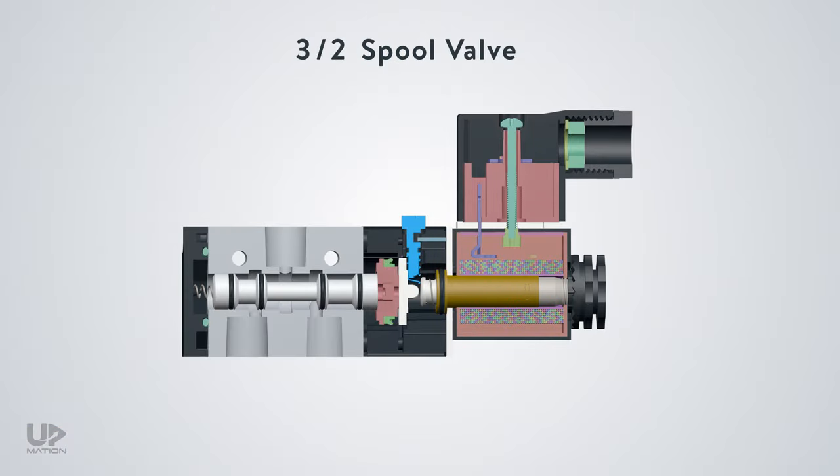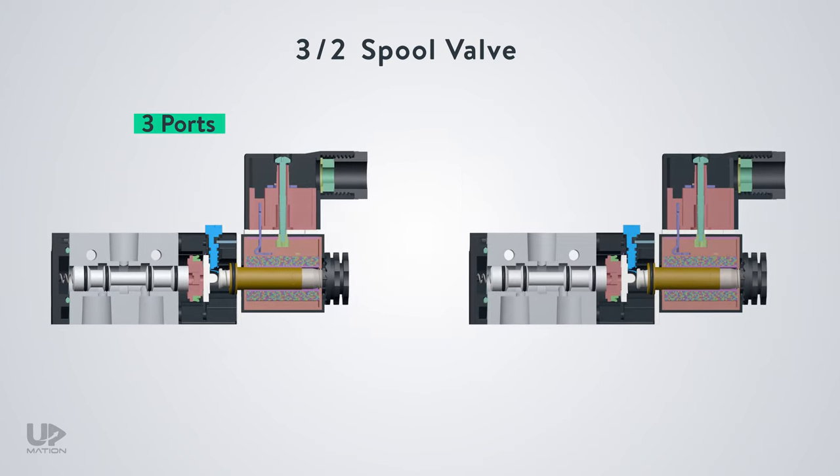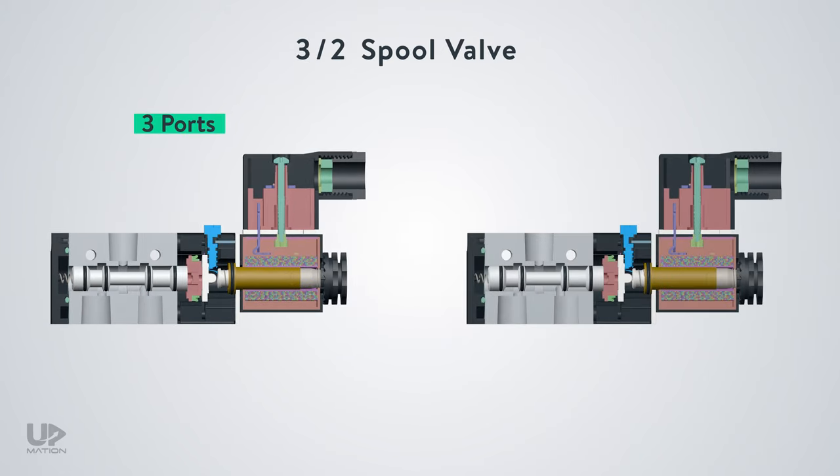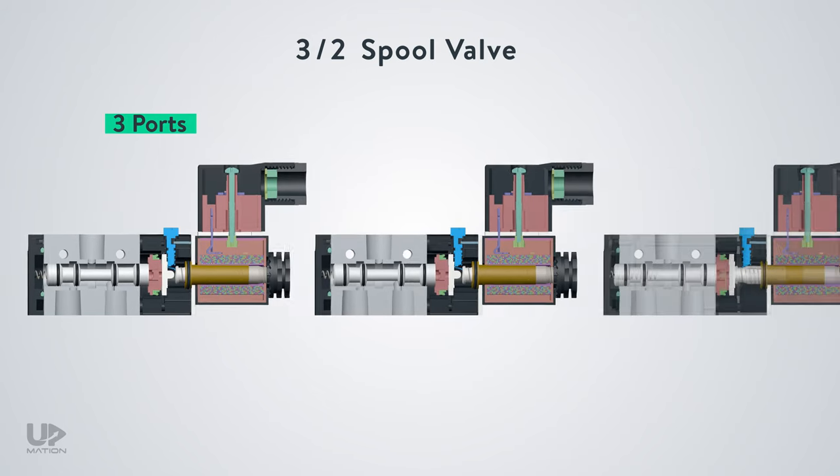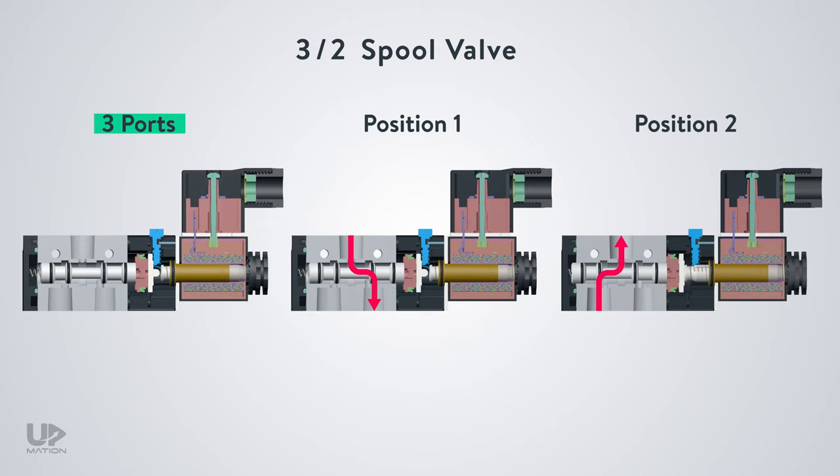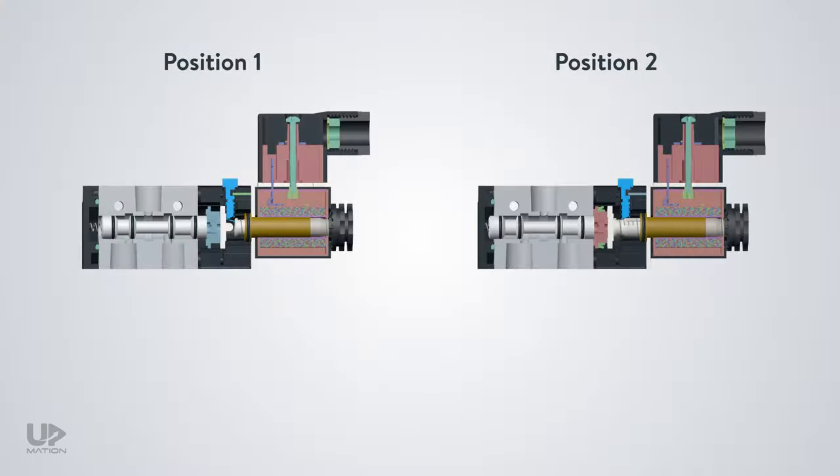We should see how many ports or ways the valve has. Here, there are 3 ports, right? That's why the first digit is 3. Second of all, we should specify how many positions the spool can take within the valve. Or, in other words, how many flow paths this valve has. The answer will define the second digit. As you see, this valve has two positions.